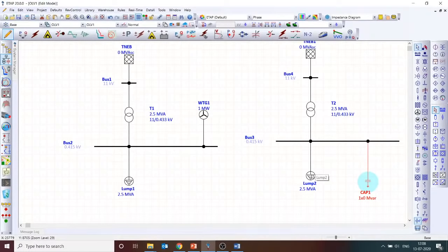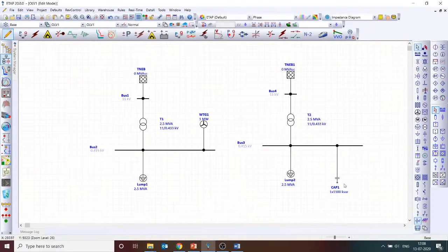So the demand is about 1500 kVAR. So approximately they will put 1000 kVAR or 1100 kVAR, right? I'm putting it in kVAR. I'm putting 1100 kVAR, and probably you need to look at what the voltage is also. That is the most important thing. Okay, so I have connected a 1100 kVAR capacitor to check what the power factor is.